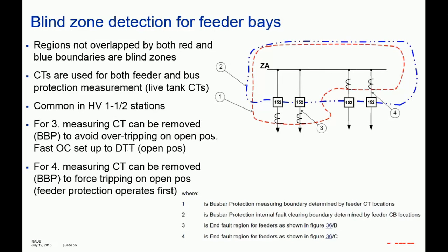A different look, a different scenario like this. Of course, this is for illustration of the principle purposes only. So it doesn't really happen this way, because when you design the station, you would definitely align the CTs on the same location. If you would put the CT on the north side of the breaker, then you would put the CT the same way across all breakers. You wouldn't put two CTs this way and the other two that way. This is just for illustration to demonstrate the concept of over tripping and under tripping, right?